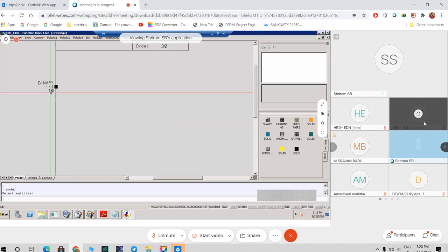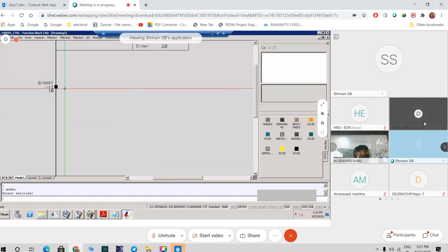Without this @, you cannot change the value from 1 to 0 or 0 to 1. So you have to once again change it in the FBCAD and then give a download. If you put this at the rate, you can directly change the value of this interface port online without having to give any download. That is one advantage this at the rate function gives.